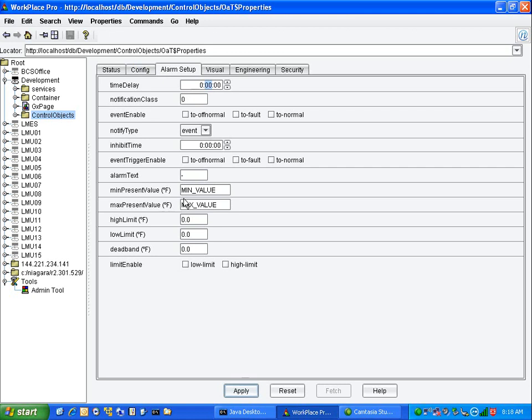We used to have problems in the early days where, if the alarms were in the UNCs, sometimes your acknowledgement would get stuck, and you couldn't acknowledge them because you acknowledge them from the server, and if the server couldn't get that message down to the UNC, you'd have what's called a stuck alarm. I haven't seen that happen in a lot of years, but ever since then, we've just been putting them in the server, and we stick with it.